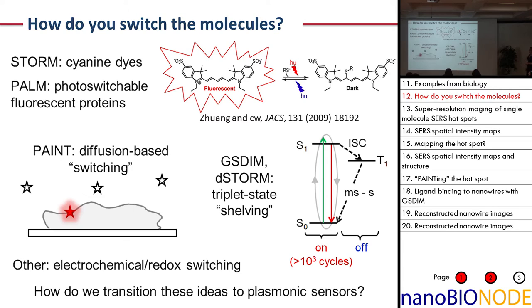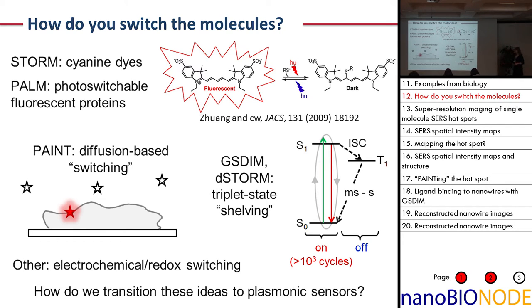Alternatively, there are techniques like GSDIM - also known as dSTORM - based upon triplet state shelving of your dye. You take advantage of the natural photophysics of the molecules so that instead of going through multiple ground-to-excited-state transitions under traditional fluorescence, you force most molecules to inter-system cross into a dark triplet state and hold them there. If you can drive most molecules into this dark triplet state, they'll remain off, and you wait for molecules to stochastically relax back to the on state where you can collect fluorescent photons and localize the emission. There are also strategies based on electrochemical or redox switching.